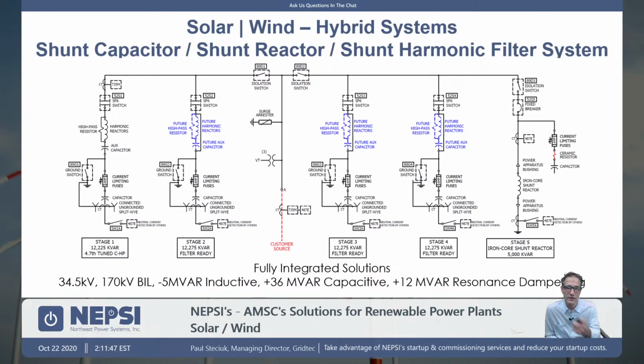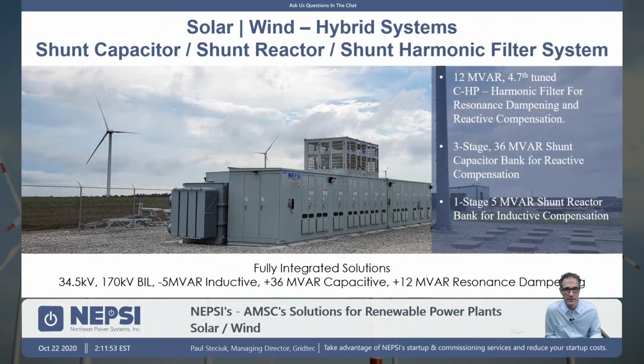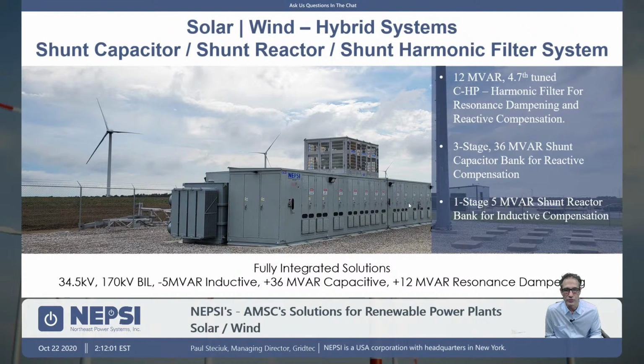So this is a fully integrated solution. It has a lot of advantages. Just looking at it on the surface here, you can see it's a very complex solution, but it's in a very small footprint. This is a very small enclosure system. If this was an open rack system, you would have air core reactors for both the filter and the shunt reactor stage. You would have elevated structures for all the capacitors, and it would take up a football field. Realistically, it would take up a football field.